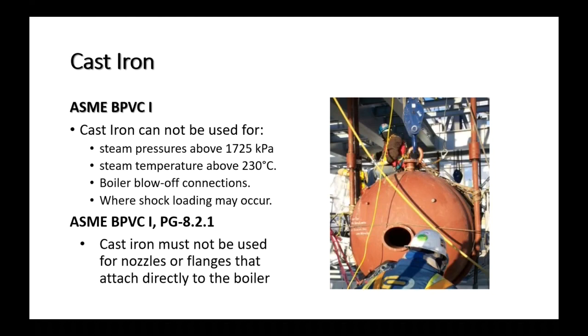Regarding cast iron: the ASME Boiler and Pressure Vessel Code says it cannot be used for steam pressures above 1725 kPa (250 psi), temperatures above 230°C, for blow-off connections, or where a shock load may occur.